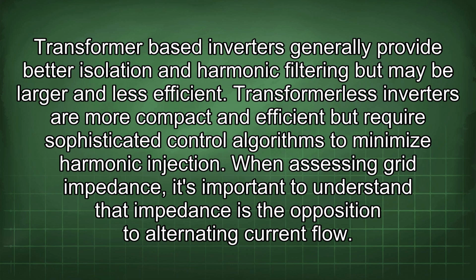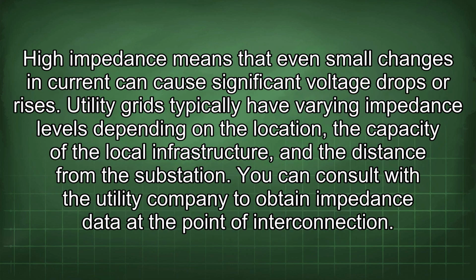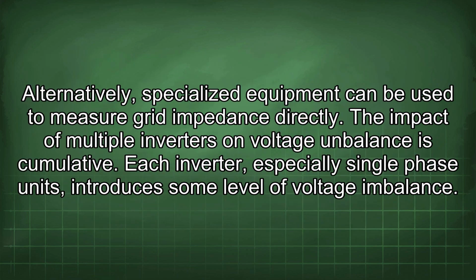When assessing grid impedance, it's important to understand that impedance is the opposition to alternating current flow. High impedance means that even small changes in current can cause significant voltage drops or rises. Utility grids typically have varying impedance levels depending on the location, the capacity of the local infrastructure, and the distance from the substation. You can consult with the utility company to obtain impedance data at the point of interconnection. Alternatively, specialized equipment can be used to measure grid impedance directly.